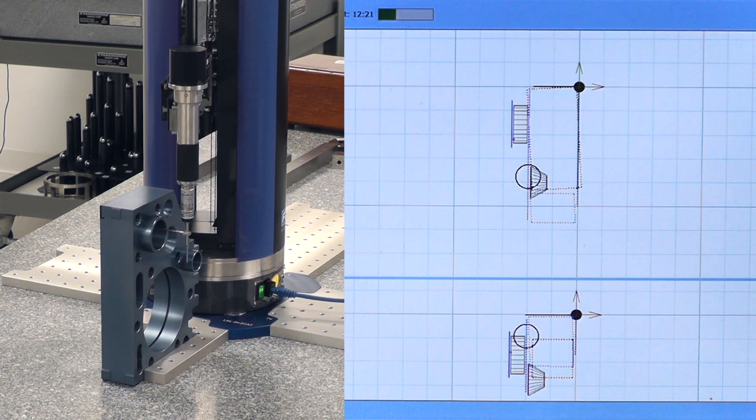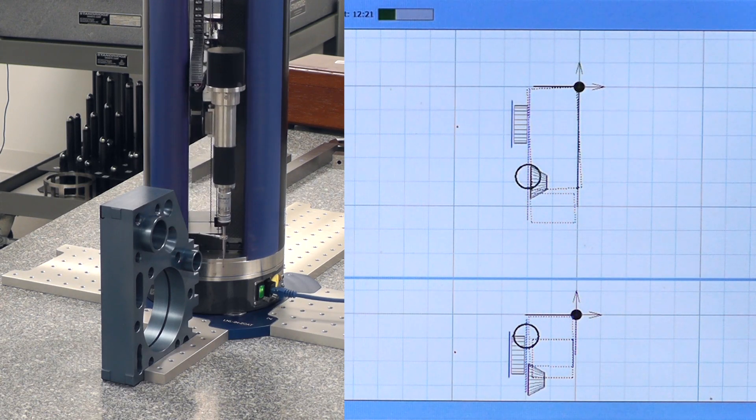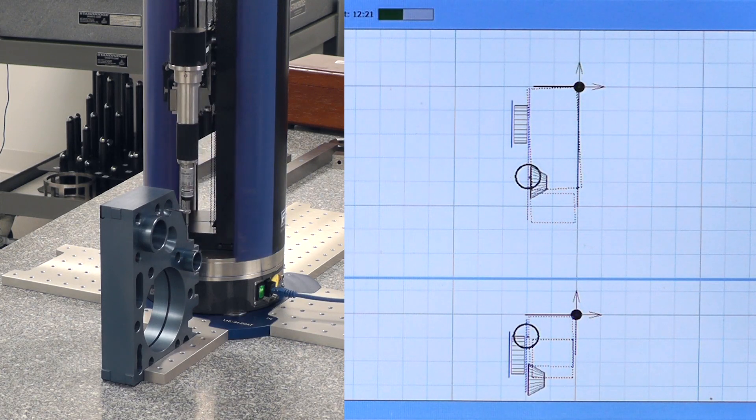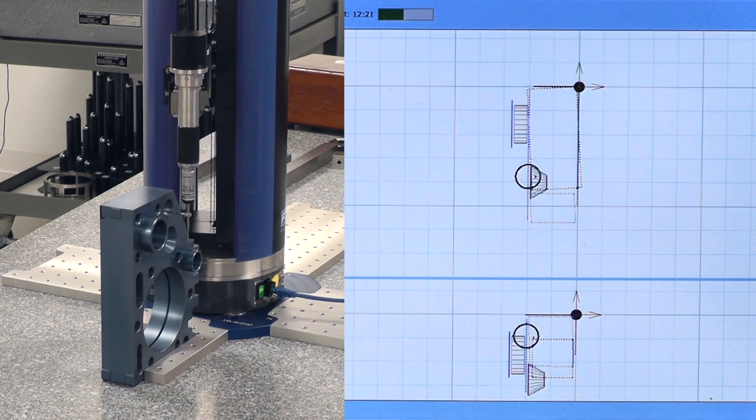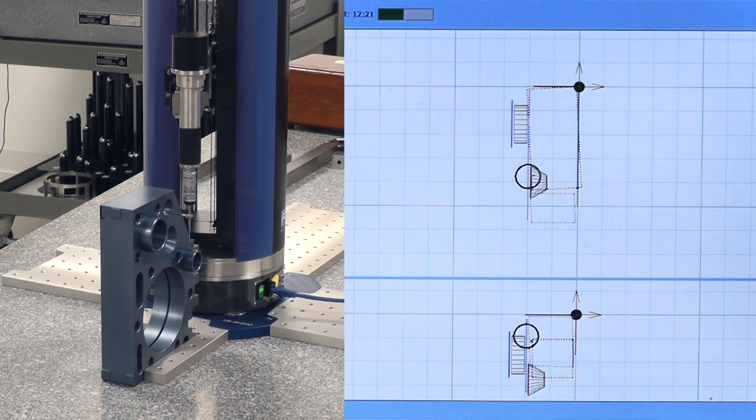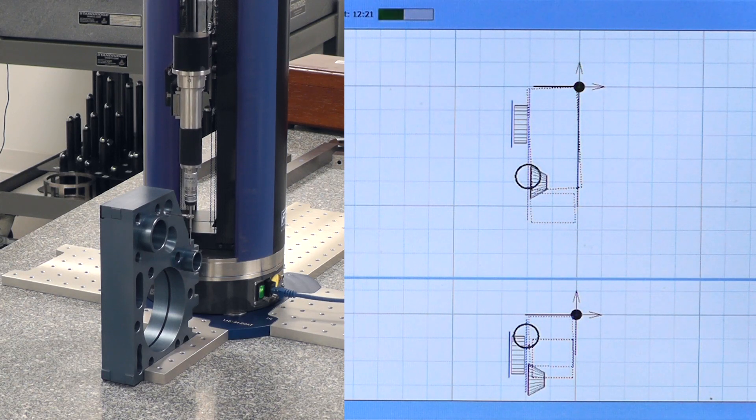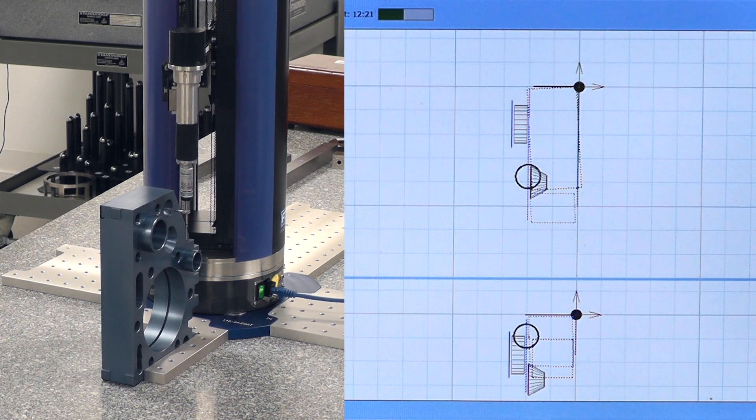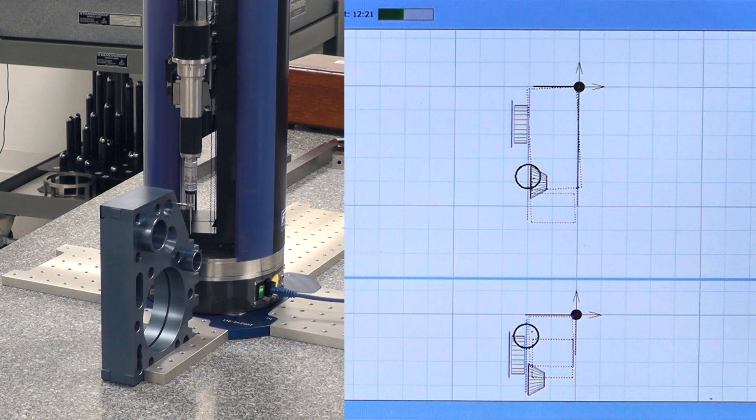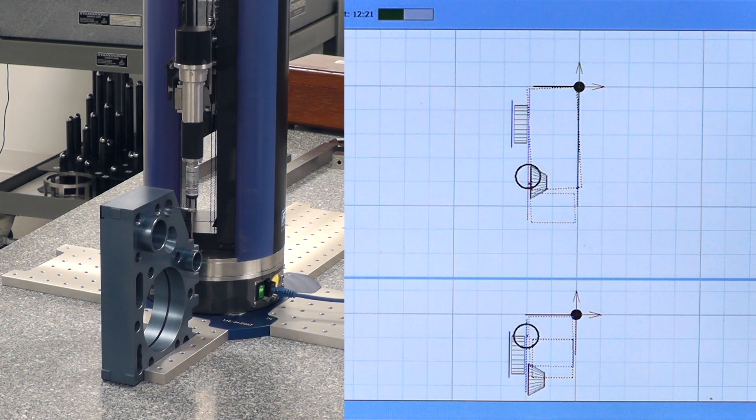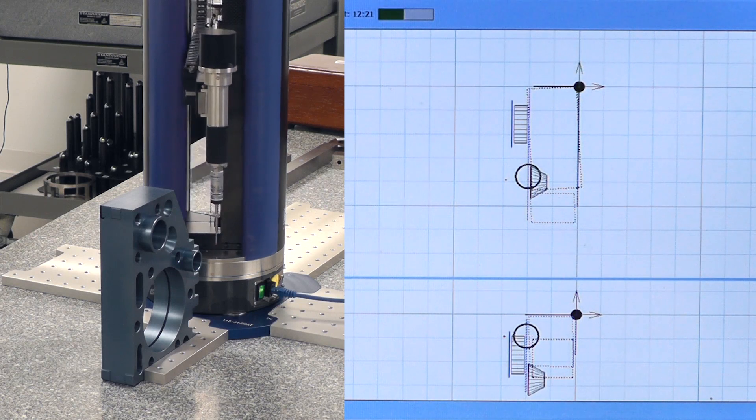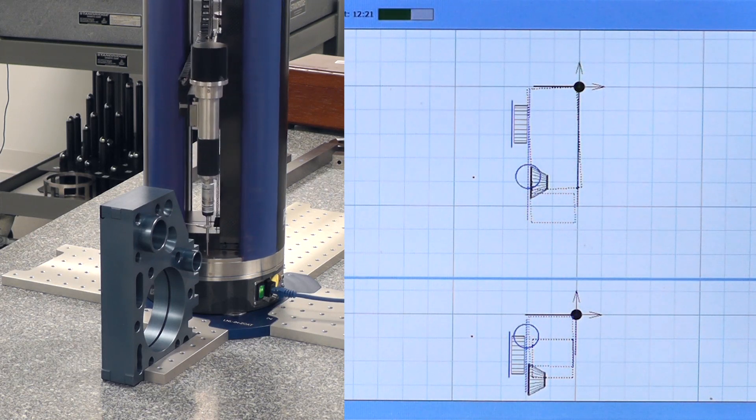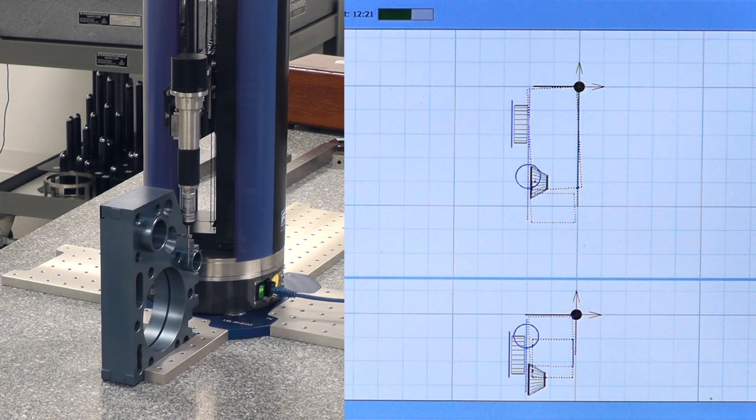The next dimension is going to do that same sphere we did. But again, we're only using the horizontal probe. But it's the same process. We're going to go in the first time, manually teach it where to take points. And now it's repeating it and archiving the data. It's doing simple statistics in the background as well. Those can be called up at a later time. Now it's going to go down. It's going to do that cone, using the horizontal probe.